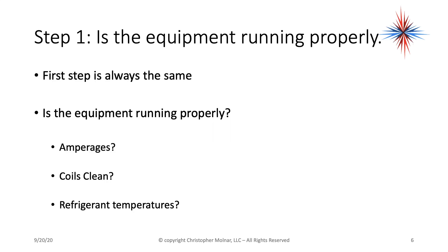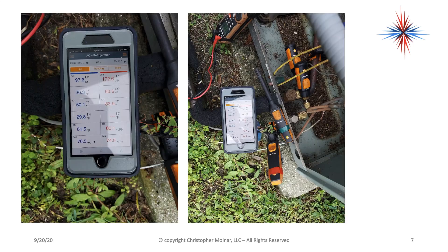Step one is always the same. We start off with: is the equipment running properly? Where are the amperages? Are the coils clean? What are the refrigerant temperatures? What are the pressures? Does everything add up? We take pictures and we take readings that also follow time.